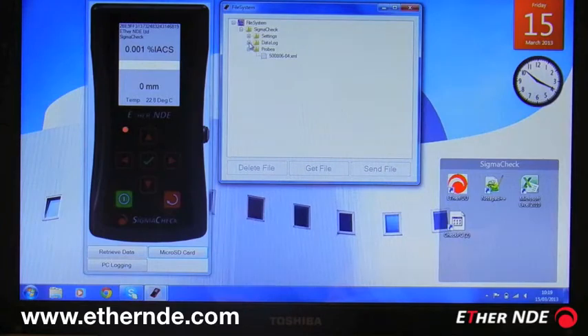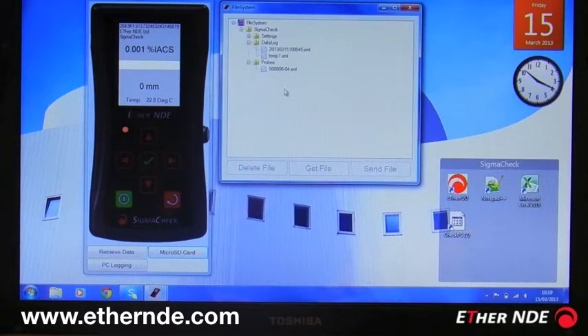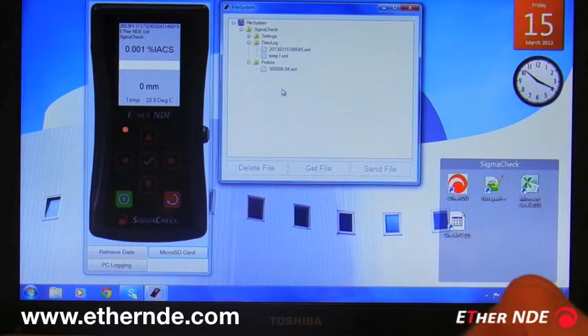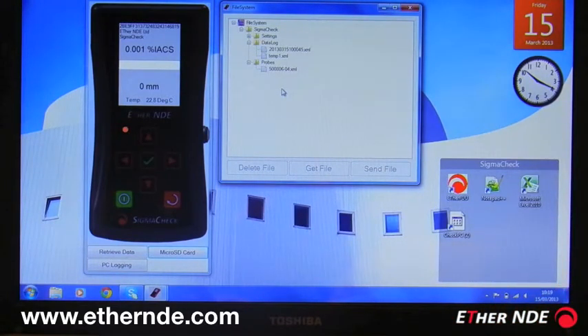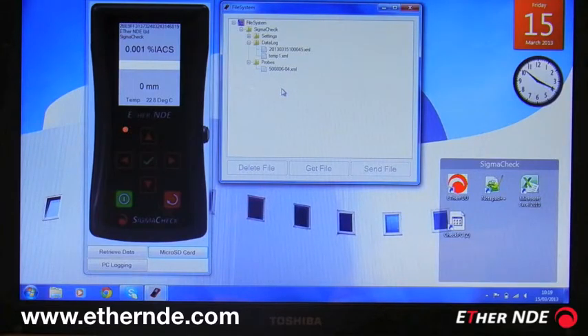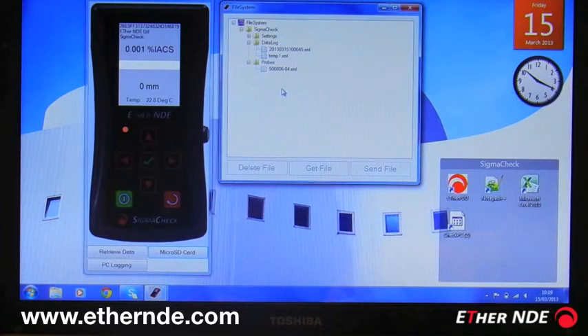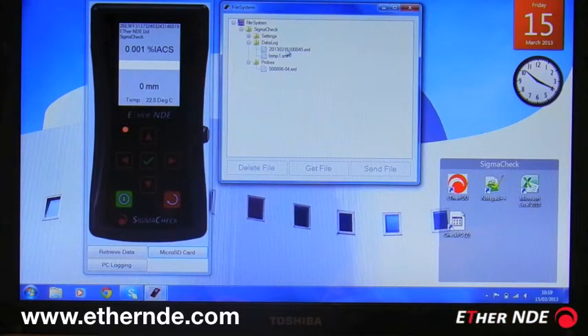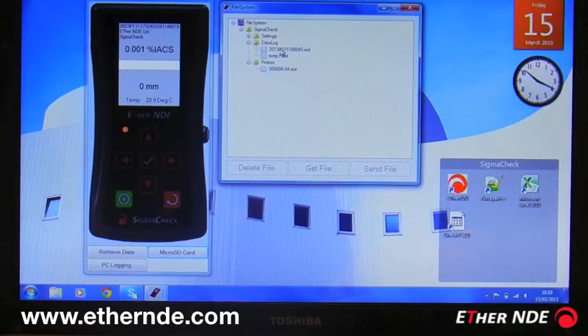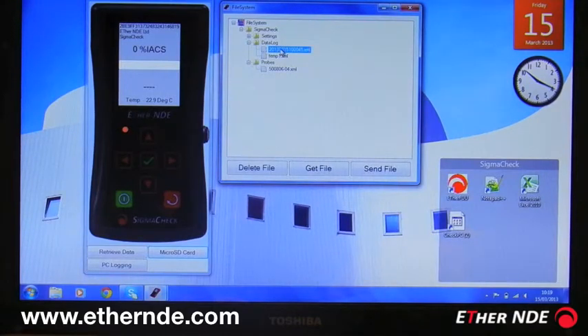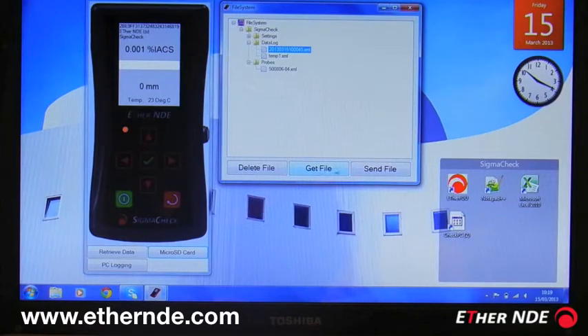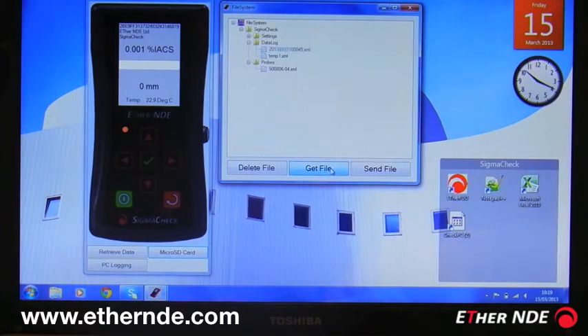And finally the data log folder. Now during data logging there is an option to store to RAM or to a micro SD card. Any files that are saved to the card are saved in this directory here. So this is the process of extracting the data. If I click on the file name, the buttons at the bottom now become highlighted. So I can click on get file.